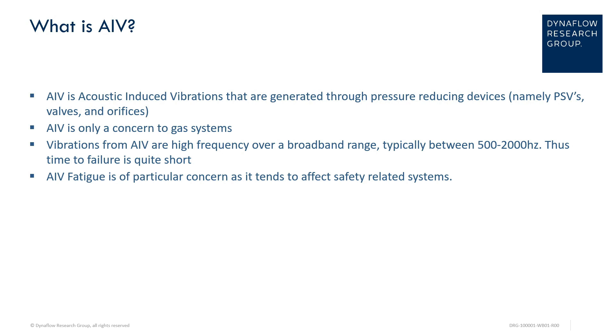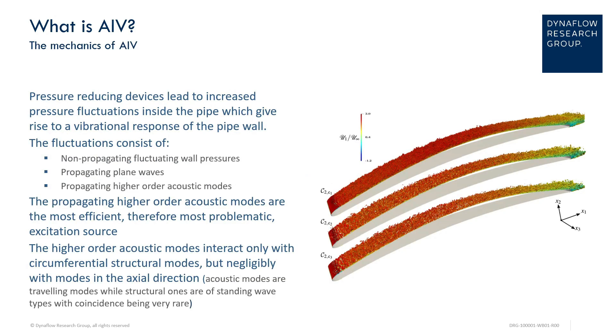Due to this high frequency, the time to failure is often quite short, being a matter of minutes, hours, or days. AIV mechanics are as follows: pressure-reducing devices lead to increased pressure fluctuations within the pipe, which give rise to a vibrational response of the pipe wall.